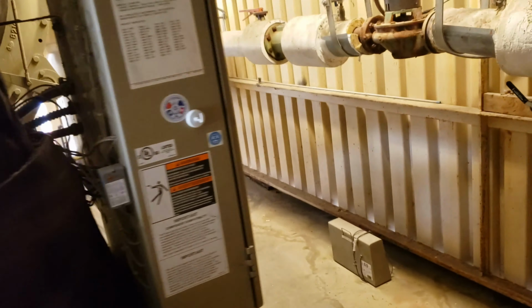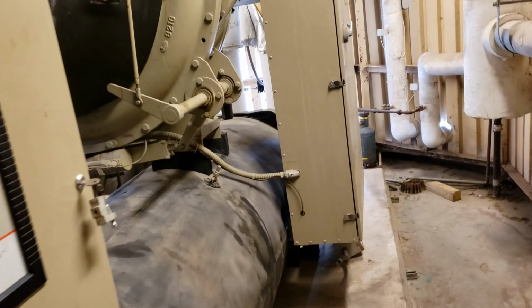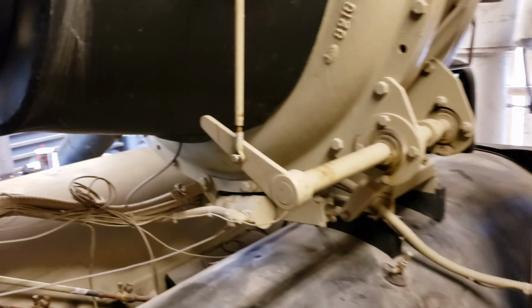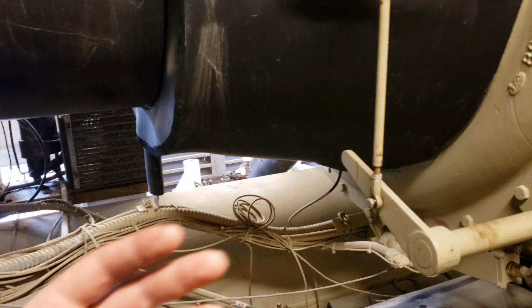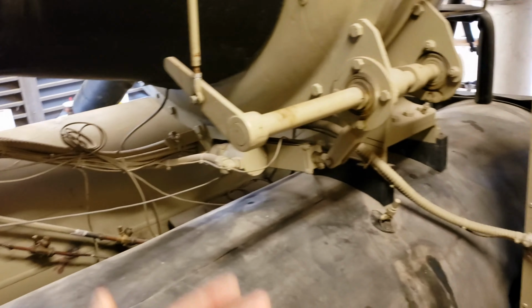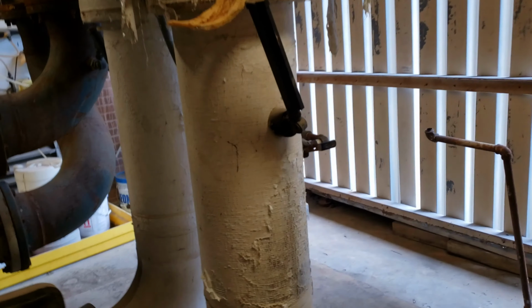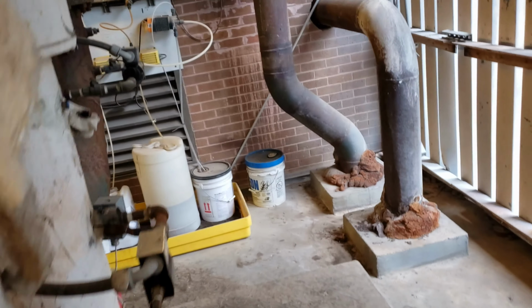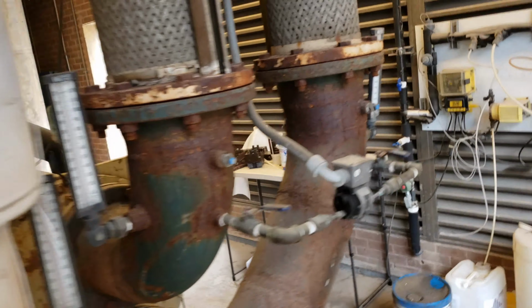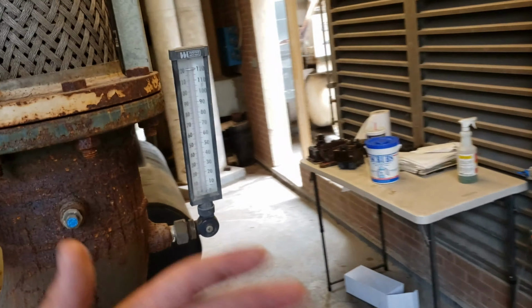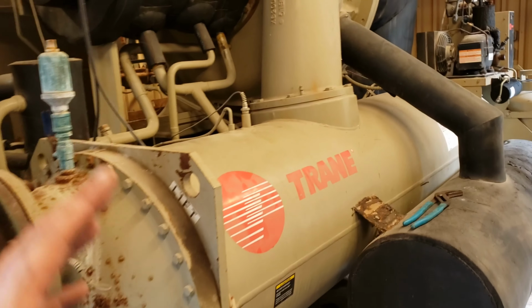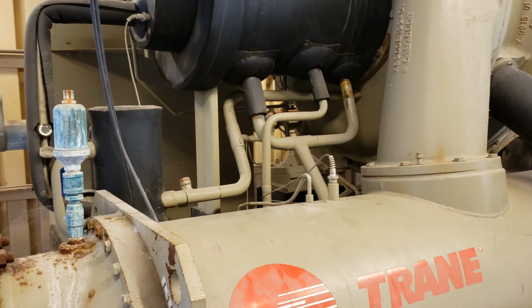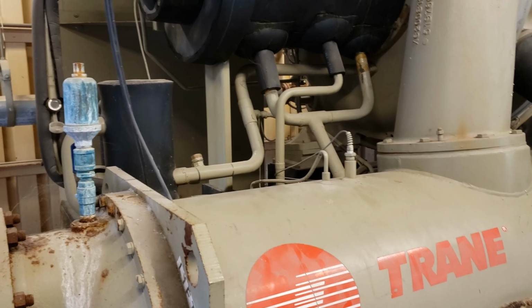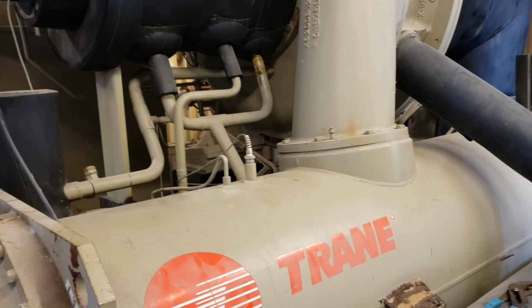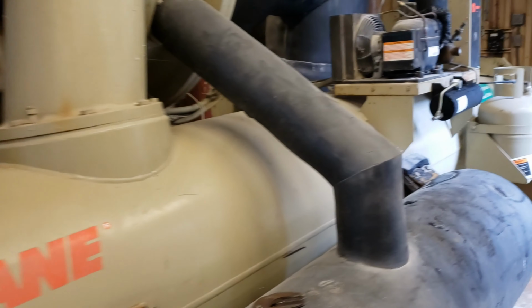That just tells you what little maintenance and work had actually gone into this chiller. So it's extremely rewarding to put so much work into it. I think I spent 2 or 3 solid days just plugging away at this thing little bit by little bit, making a correction, letting it run, seeing how it responded, trying to let the purge catch up, making more corrections, and so forth. This chiller is still not 100% out of the woods — there are still some automation issues, some other minor things. But where we are at is this thing is 100% operational and savable, and there's no need to do anything major other than just make it right.